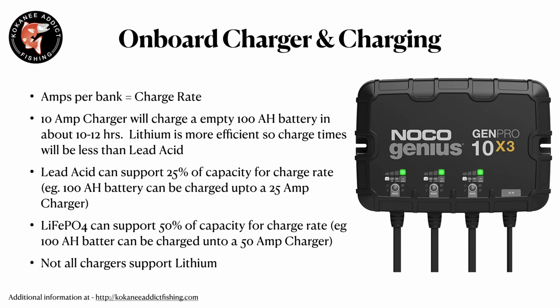Another couple things to keep in mind: lead acid can support 25% of the capacity as the charge rate. So if you have a 100 amp battery, you can charge up to 25 amps, or use a charger that will charge up to 25 amps. For a lithium battery, it will support up to 50% of the charge rate. So if you have a 100 amp hour battery, you could get a charger that would charge up to 50 amps. One thing to note there, even though you can charge it that fast, charging it that fast all the time can have some negative effects also.